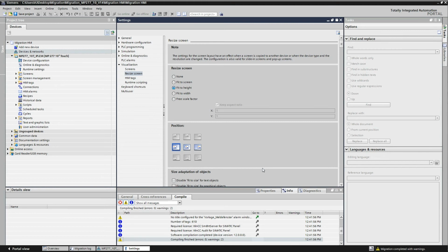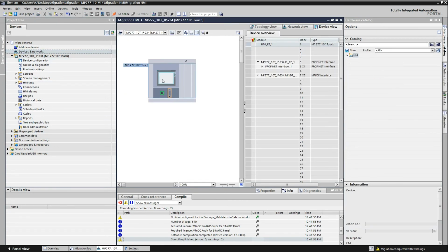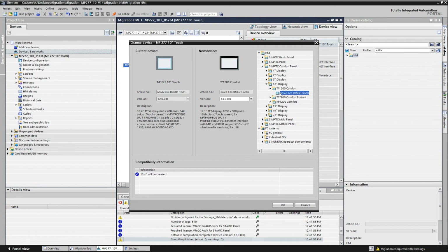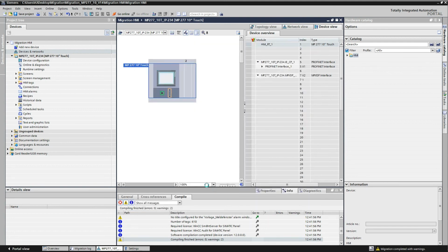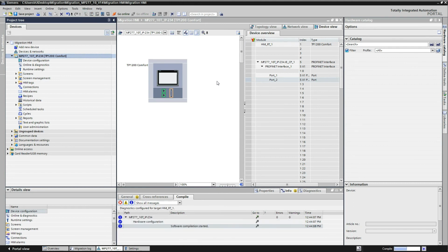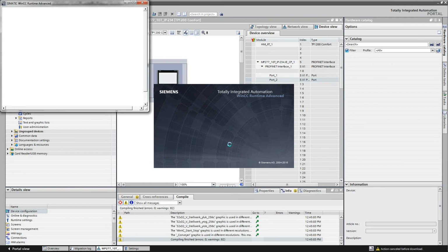Once I've picked how I want the layout to migrate in, I can go back to my Devices and Networks tab. Right-click on the HMI and hit Change Device. Select the new panel. In this case, an MP277 10-inch is replaced by a TP1200, which is a 12-inch widescreen comfort panel.